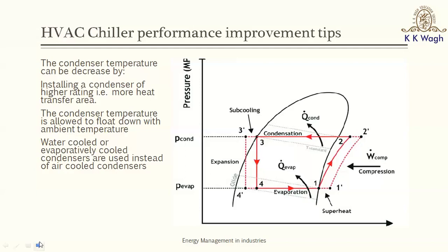The second thing is that we can choose a water-cooled condenser or even an evaporatively cooled condenser instead of an air-cooled condenser, because with a water-cooled or evaporatively cooled condenser, the higher heat transfer coefficient as compared to air-cooled condensers would give you better performance.